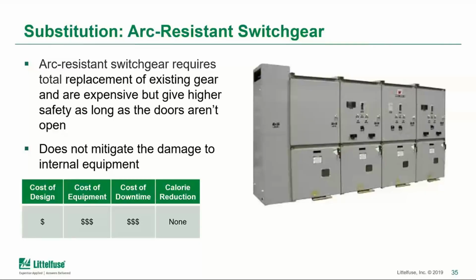This type of gear does have a cost associated with it, of course, based on the additional build that has to be done to accomplish that, as well as possibly some extra cost in retrofitting the building itself with the arc plenum. The equipment damage will still be considerable, because there is no reduction of incident energy inside the equipment itself. The internals could be significantly damaged, but you would have good protection to human life, somebody standing out front, as the equipment will contain that.